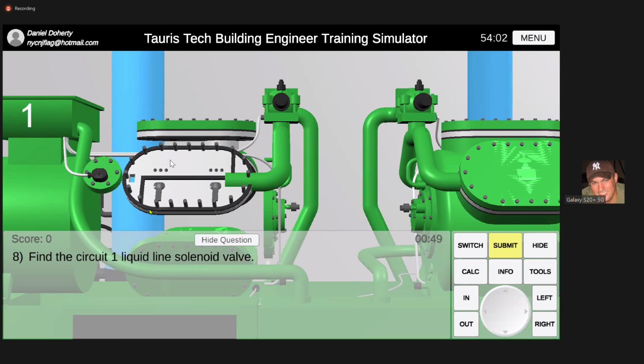On this side you had, what is it, low pressure, low temperature. This is the low pressure side, and this is the high pressure side. So you have low pressure, high temperature, superheated, because you can't send liquid into the compressor. Remember that, it has to be vapor, and it has to be superheated. If you send any liquid into the compressor, it slugs. So just because it's low pressure, that doesn't mean it's low temperature. You understand that? Because it's flashing off in here.